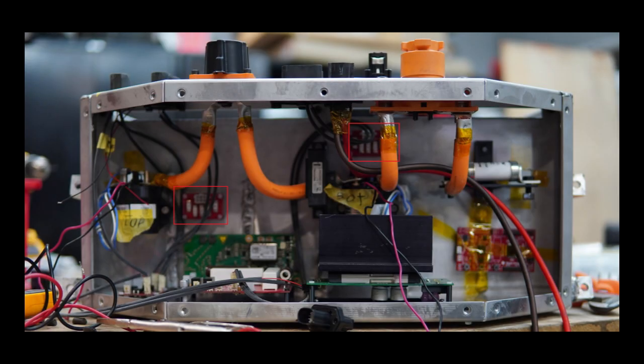This image of our high voltage enclosure under construction shows the location of the fuse boards highlighted in red. By inspection, the fuse boards are quite close to the inverter side terminals of both AIRs and are within 150 millimeters as required by the rules.